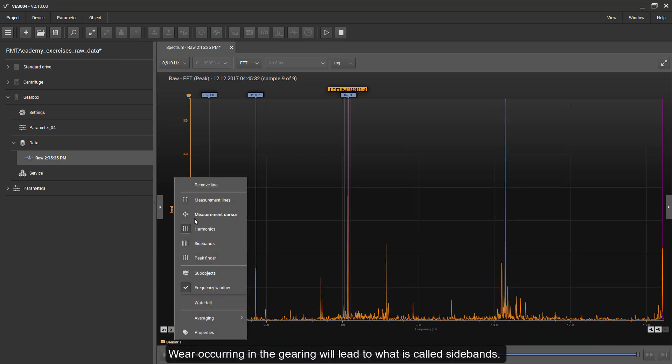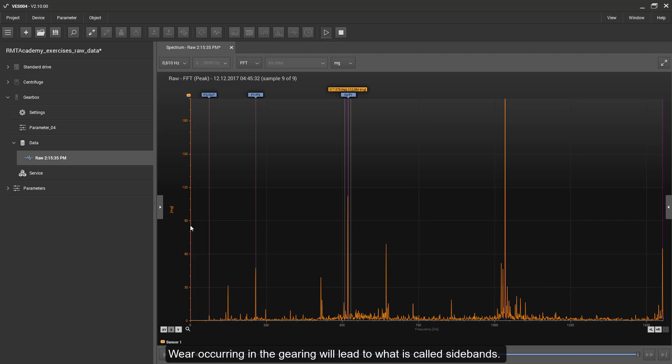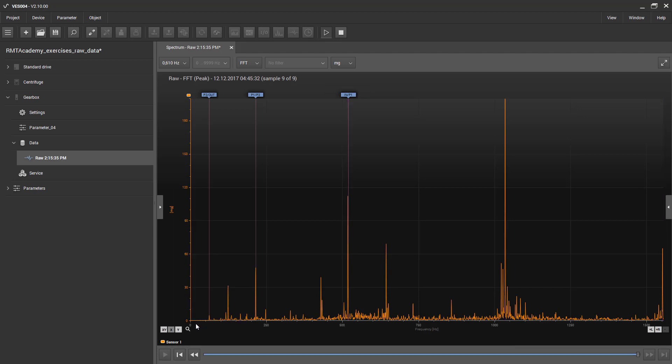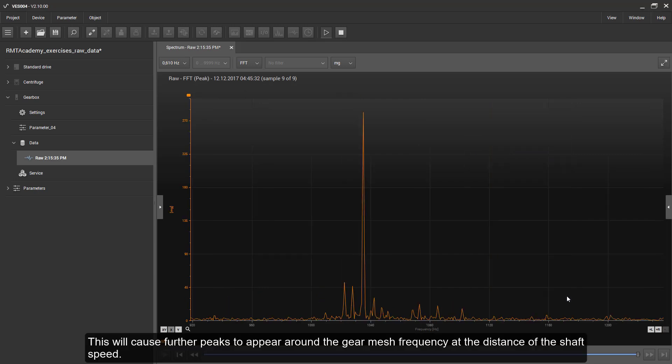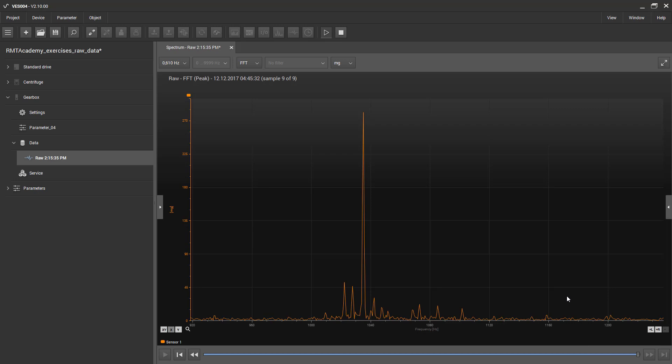Wear occurring in the gearing will lead to what we call side bands. This will cause further peaks to appear around the gear mesh frequency at the distance of the shaft speed.